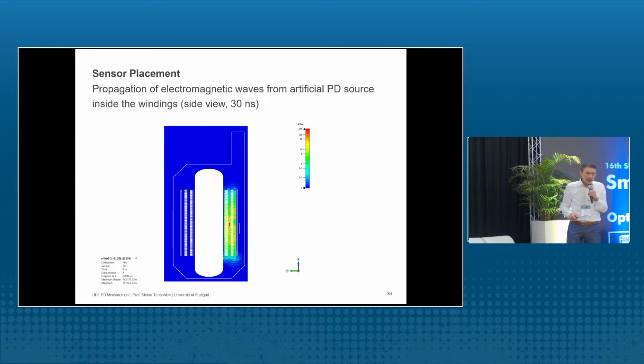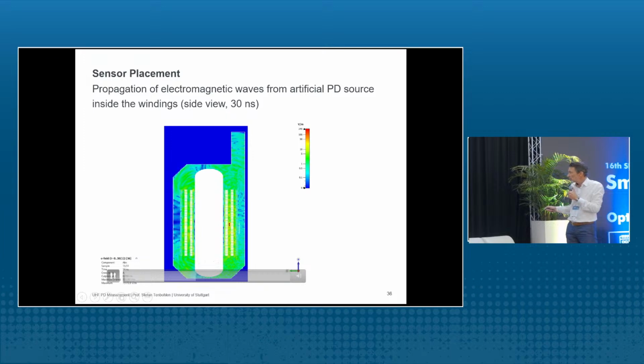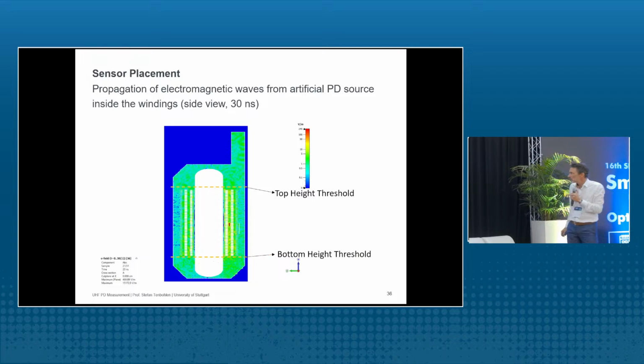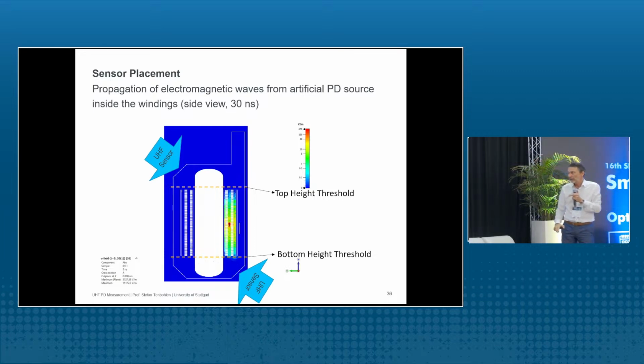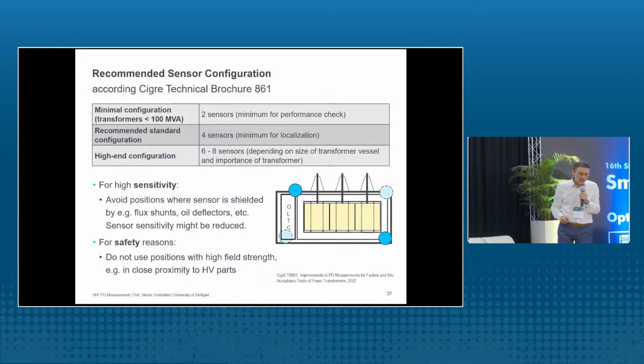Of course, then there is a question of where to install these sensors. Again, we have shown here a PD which is inside the winding, and you can see first the electromagnetic waves have to come out of the winding. Yeah, here you see it's coming out on top and on the bottom of the winding, and therefore we suggest to install the sensors above the upper end of the winding or on the lower end of the winding, because here the electromagnetic waves are the strongest. In total, we say the minimal configuration for a smaller transformer is 2 sensors, but for bigger transformers you can also install more to increase the sensitivity and also to localize the PD.